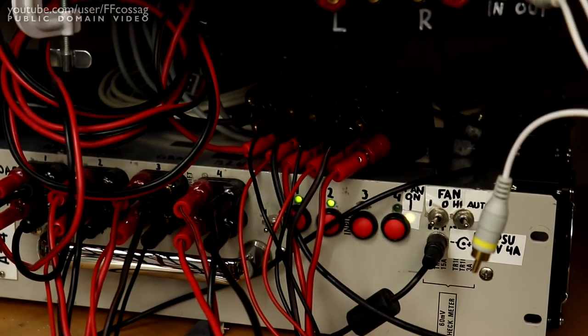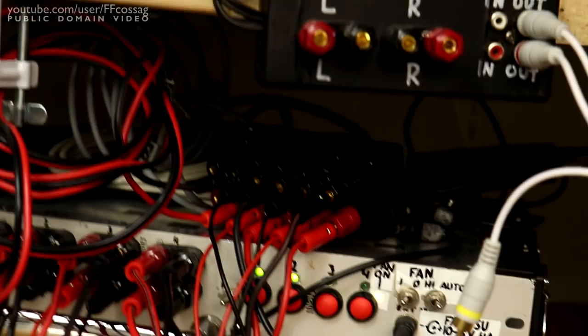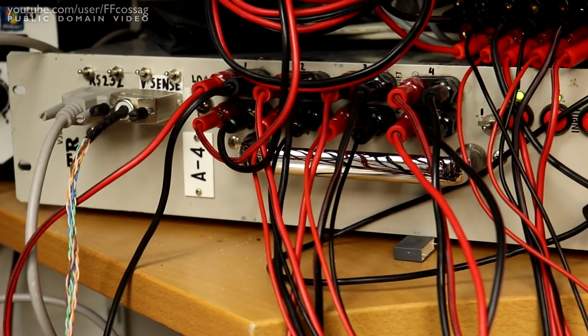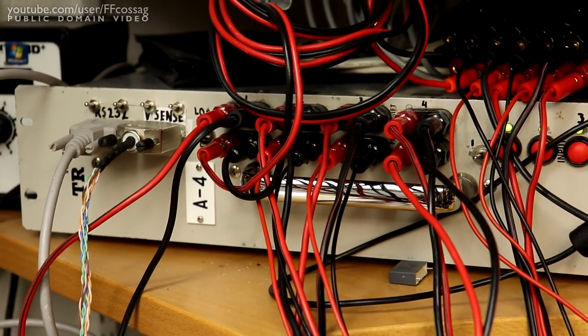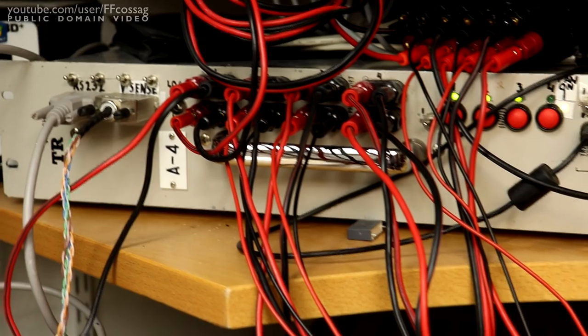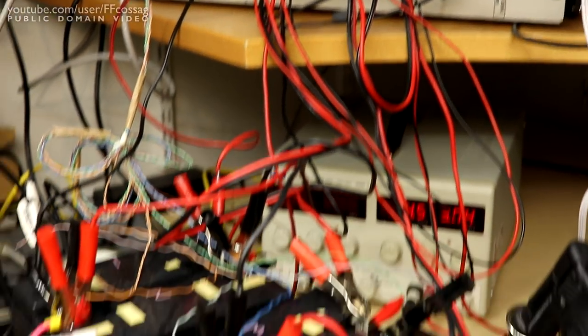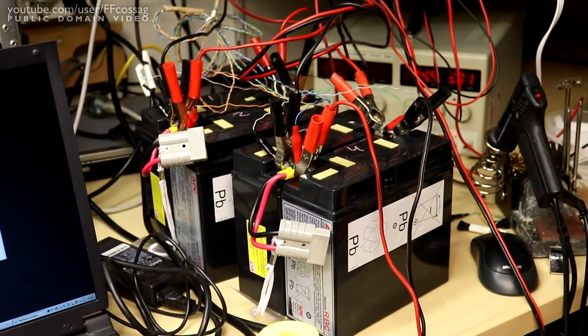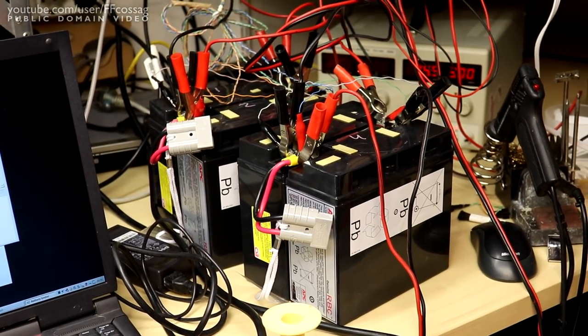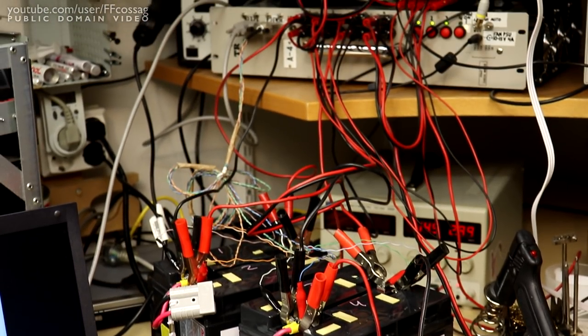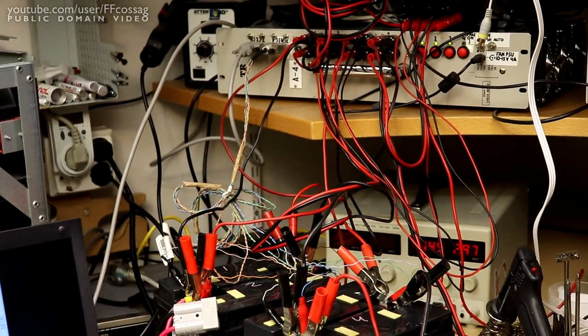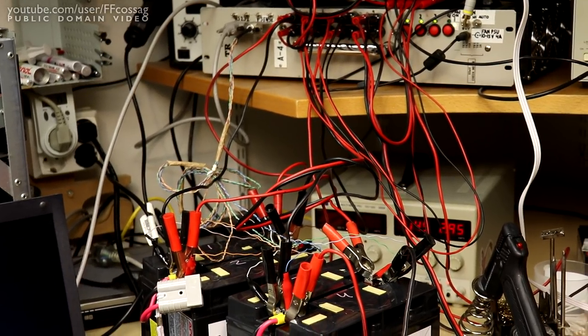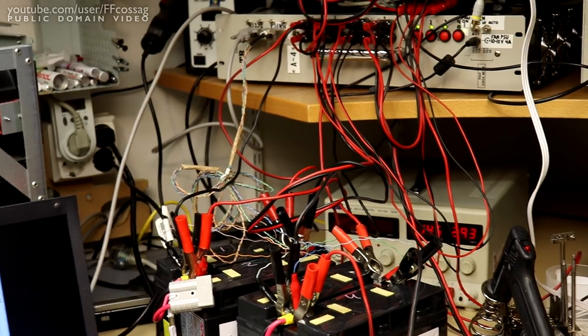This is rather finicky, not really the safest way to go about things, but we do seem to have everything wired up correctly. I've removed the battery fuses to make these all act as individual 12 volt blocks, and I'm currently charging them with a lab power supply there at 3 amps in total. So the lab power supply is feeding into this giant block of banana plugs there which in turn is feeding to the charger inputs on the dummy load. The dummy load has the batteries connected to it as well as the voltage monitoring terminals. So I'm going to let this charge for a little while and then I'm just going to flick the big red switches, and this is going to get a 10 amp discharge overnight and we'll see just how good the shape these batteries really are. Hopefully they're decent and they can service this UPS for quite a while.